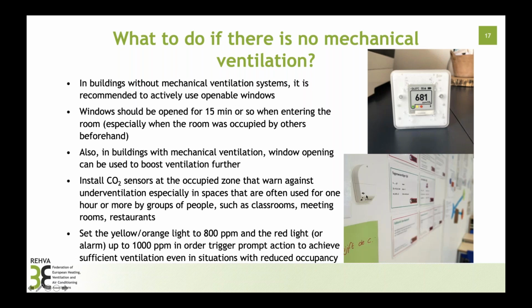So these can be relevant in the classrooms, open plan offices, meeting rooms, if there is no mechanical ventilation that is known to be operated at full speed. So in such well ventilated spaces, no need to install these, but this is a recommendation if naturally ventilated spaces are in question. And because of the epidemic, we have recommended lower ppm values than commonly, so that yellow will start from 800 ppm absolute value and 1000 will be the limit for the red. So if it is higher than 1000, then it's time to open the window or to leave the room. So this can help a situation in spaces where you commonly don't know how well these spaces are ventilated.